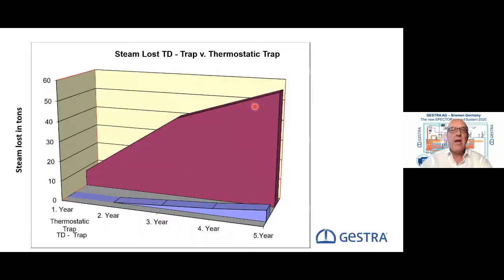Much more interesting is what happens over the next 5 years, over a certain amount of time. The time factor is interesting. When the plant runs 5 years, and we do not consider the aspect of dirt or water hammer problems, just how the working principle behaves under normal condensate quality conditions, the TD traps, for instance the thermodynamic steam traps, increase the loss of live steam significantly. This graph shows the accumulated loss over 5 years. Here we have a thermostatic, bimetallic or capsule type steam trap. It increased a little bit over the years, but here, with the leakage over the seat that the plate is hammering against, the frequency of the trap will increase, and as the frequency increases, you will lose more and more steam, which is also possible to measure and is shown in this graph.